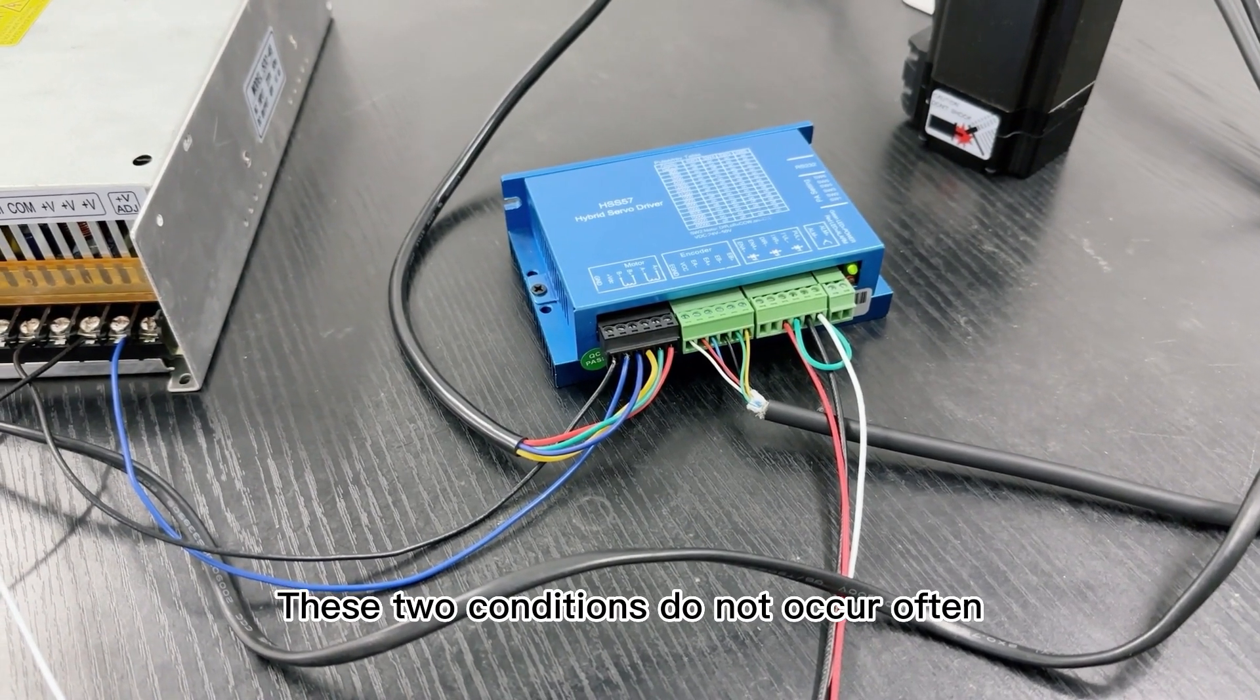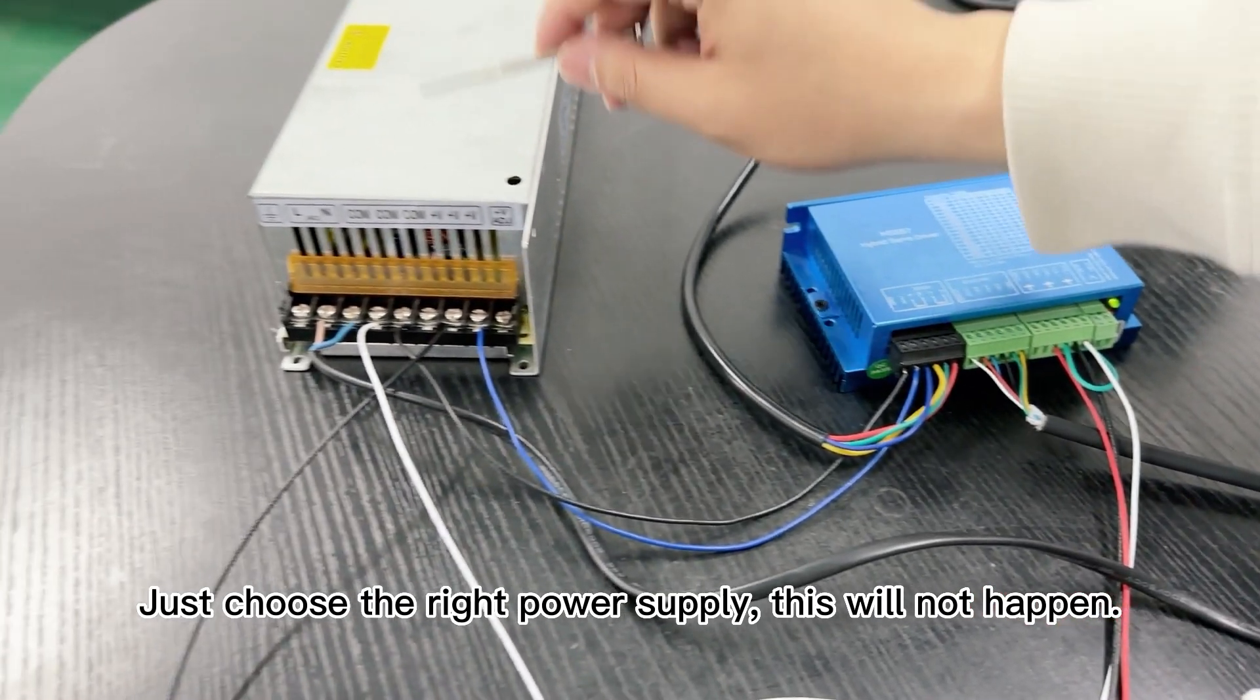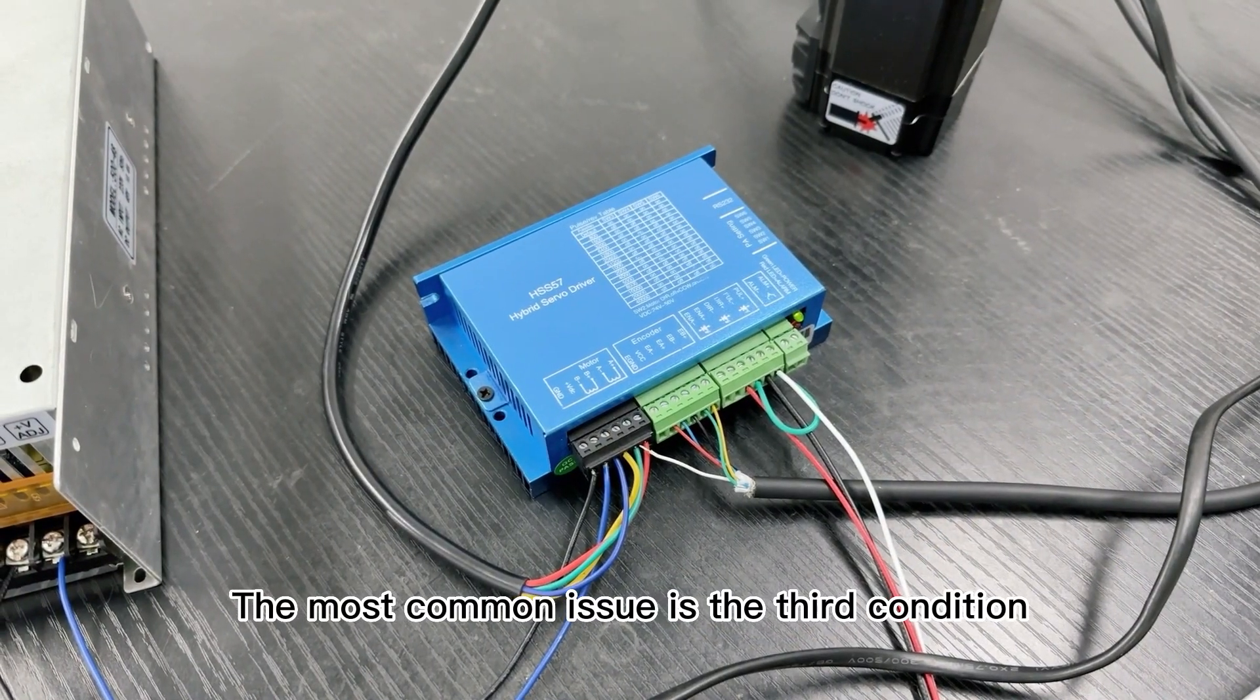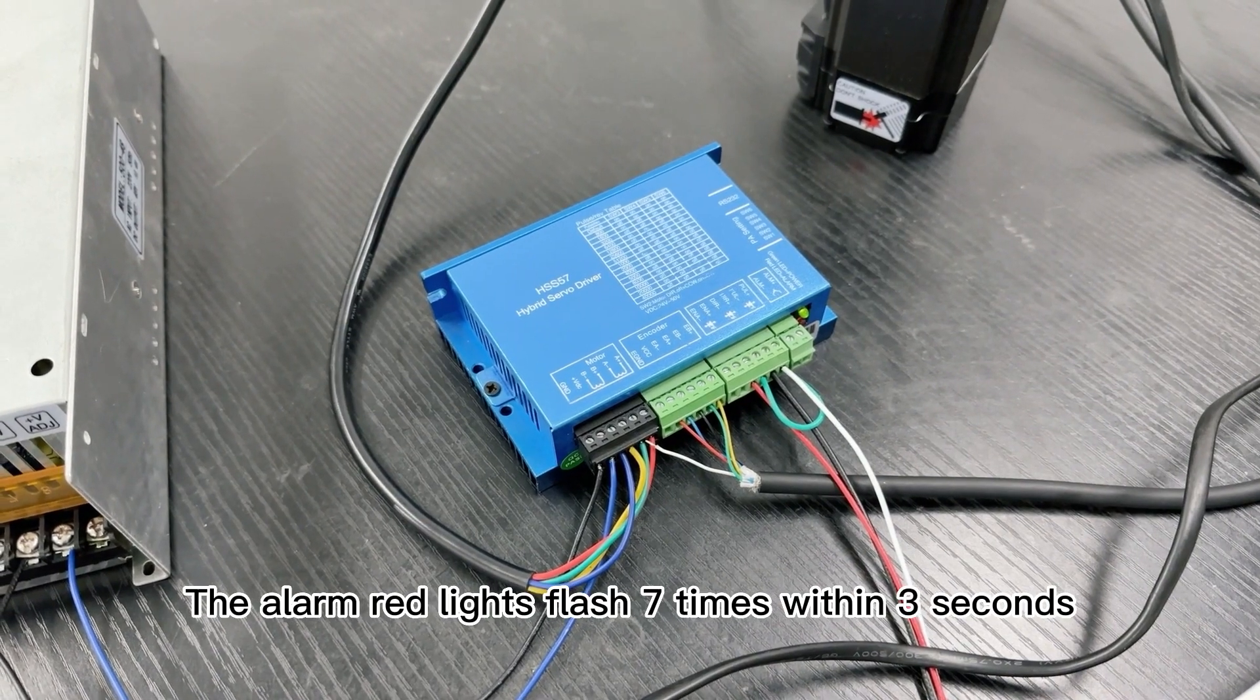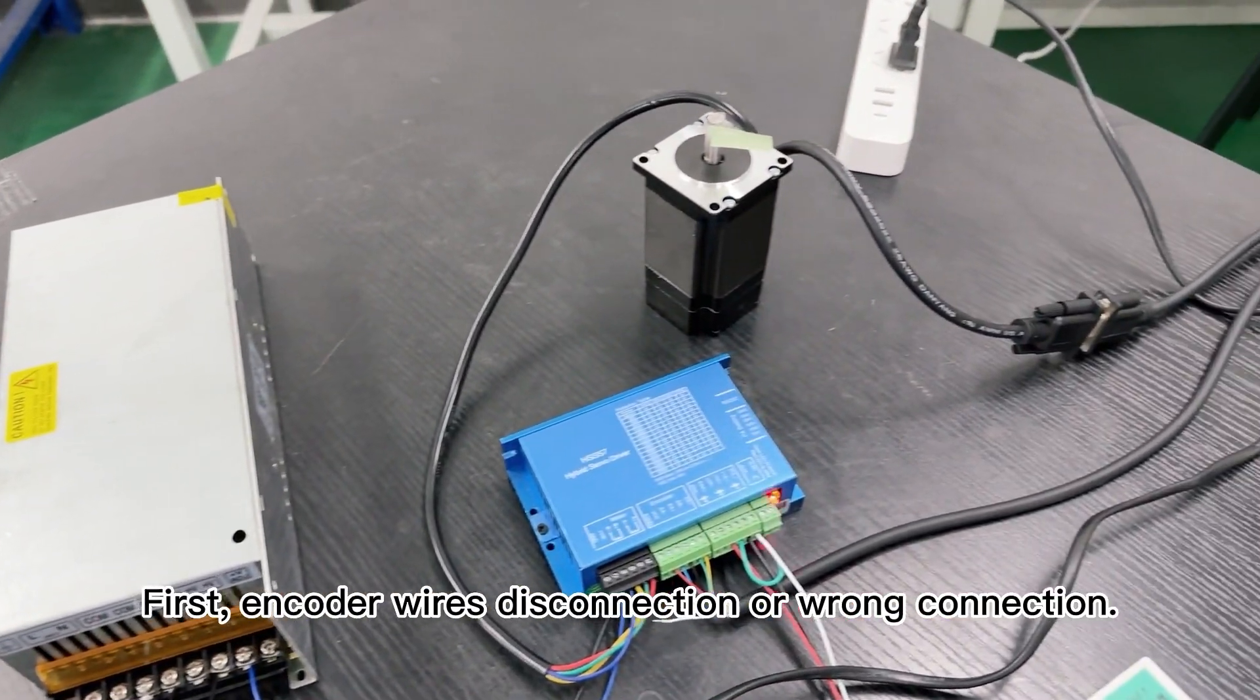These two conditions do not occur often. Just choose the right power supply and this will not happen. The most common issue is a third condition: the alarm red lights flash seven times within three seconds. This problem occurs for two reasons. First, encoder wires disconnection or wrong connection.